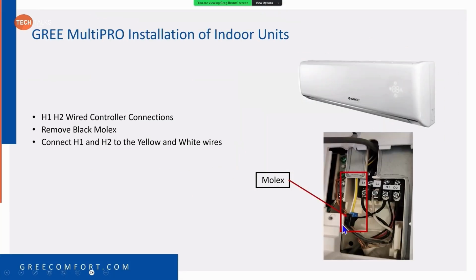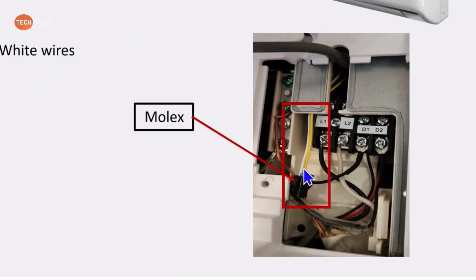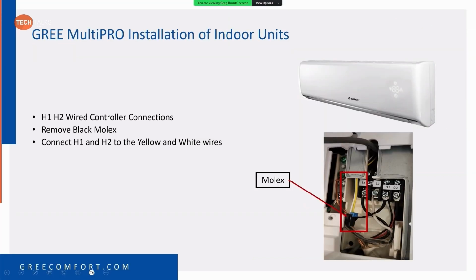On the wall mounts as well, there is no H1, H2 if you want to use a wired controller. Your H1, H2 is going to be this yellow and white wire hanging down to this Molex. Just cut that Molex plug off and connect one of your wires to white and one of your wires to yellow, and then at the controller you'll hook one wire to H1, one wire to H2. It is not polarity sensitive, so you don't have to worry about that either. If you actually took this thing apart and really looked at it like I did, you follow the wires all the way up, they're soldered onto the board at H1 and H2.